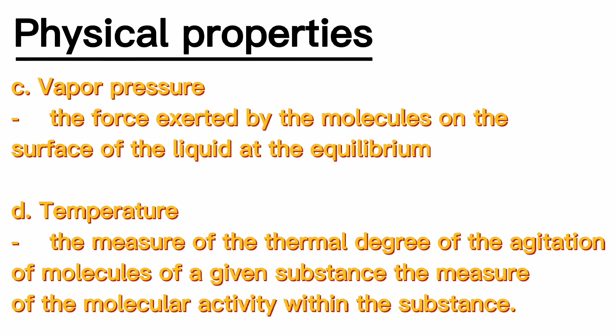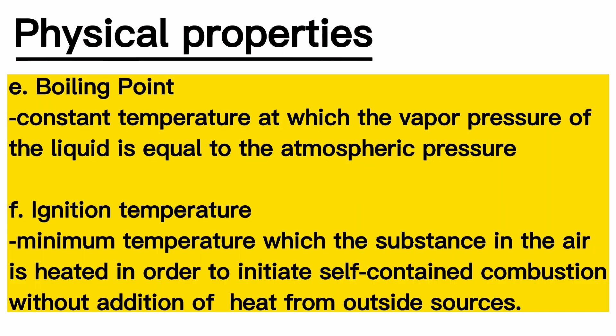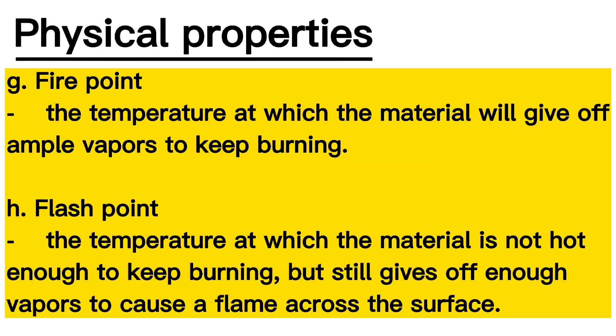E. Boiling point — the constant temperature at which the vapor pressure of the liquid is equal to the atmospheric pressure. F. Ignition temperature — the minimum temperature at which the substance in air is heated in order to initiate self-contained combustion without addition of heat from outside sources. G. Fire point — the temperature at which the material will give off ample vapors to keep burning. H. Flash point — the temperature at which the material is not hot enough to keep burning, but still gives off enough vapors to cause a flame across the surface.